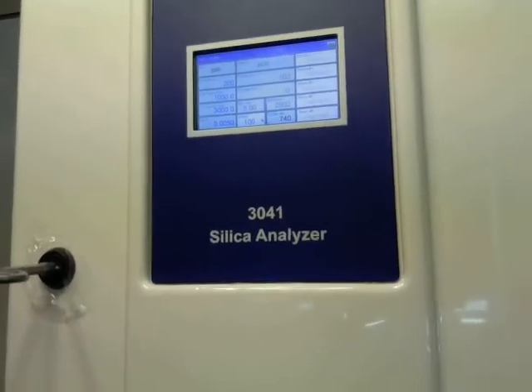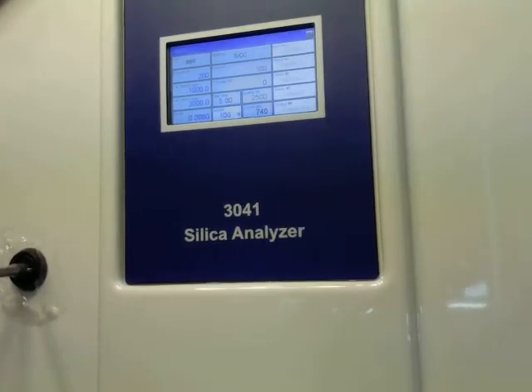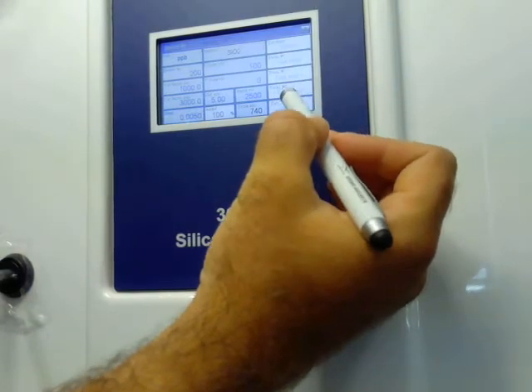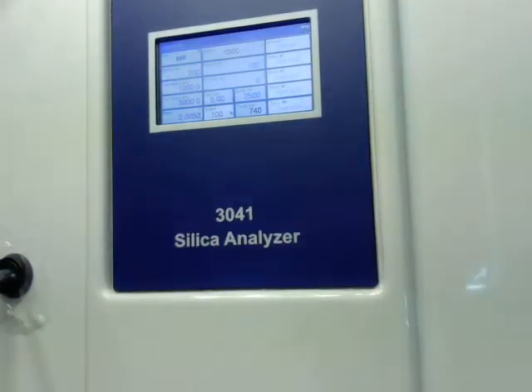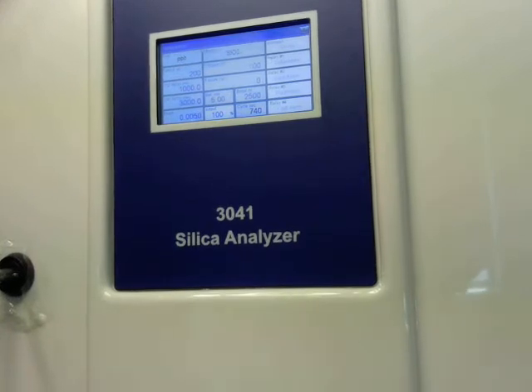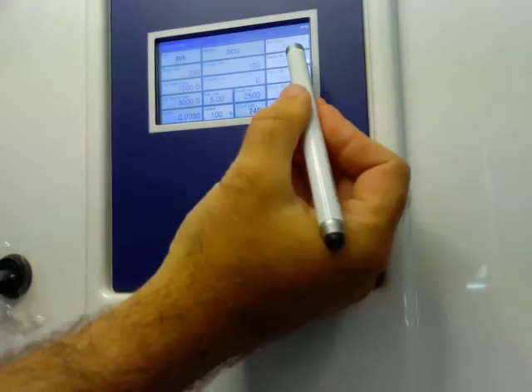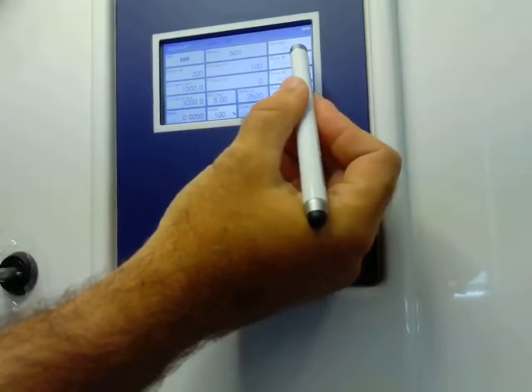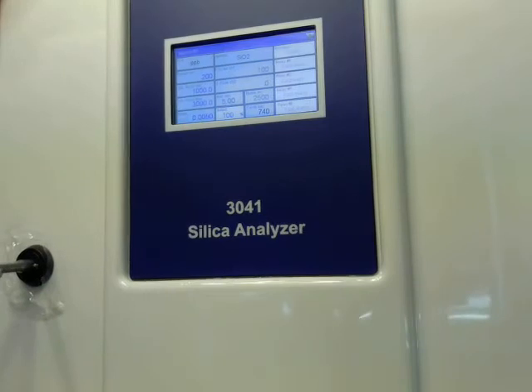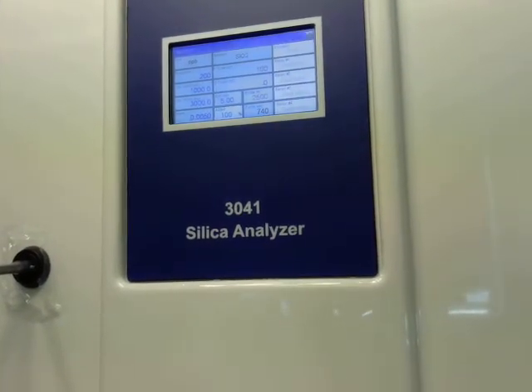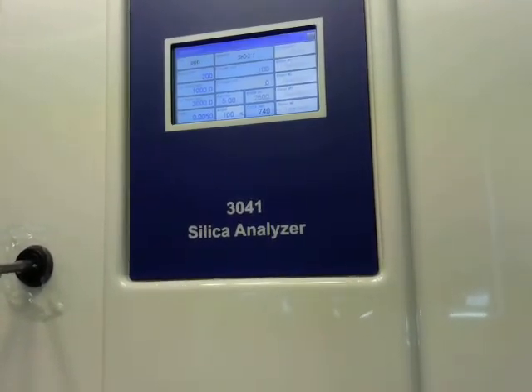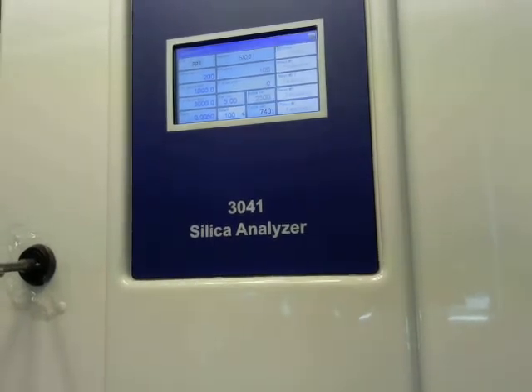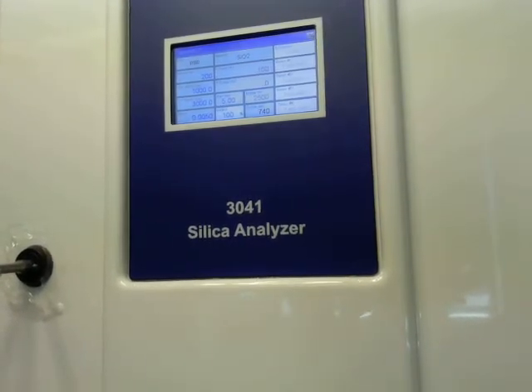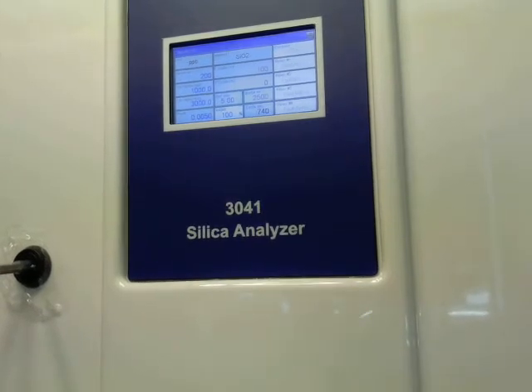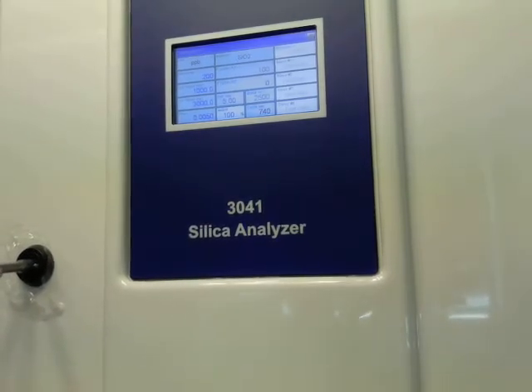Also of note on this screen, on the right-hand side, we have our various relays. Again, there's 4 relays you could put a wiring to. Not sure how well it's coming through on the camera, but if you press on that, you'll cycle through the various options you have for that relay. Again, they can be result alarm, power on, loss of flow. So if you need to wire any of that for alarm notifications, you can wire them and then set which alarm you want to be related to that relay right there.